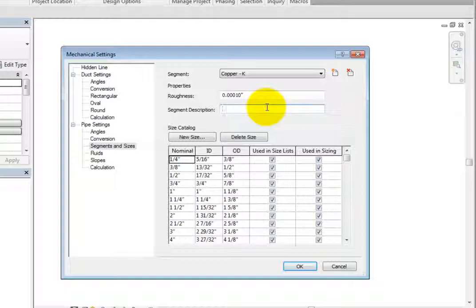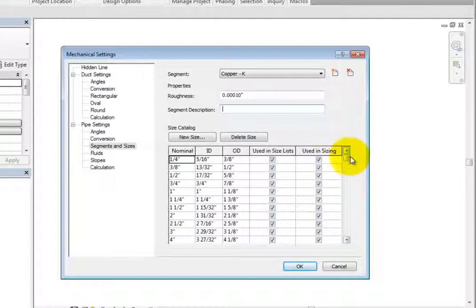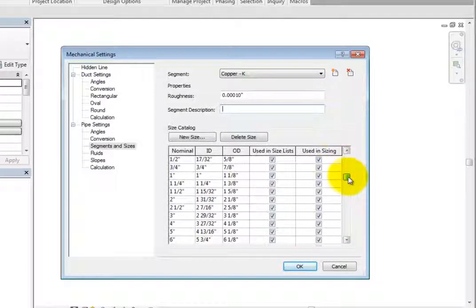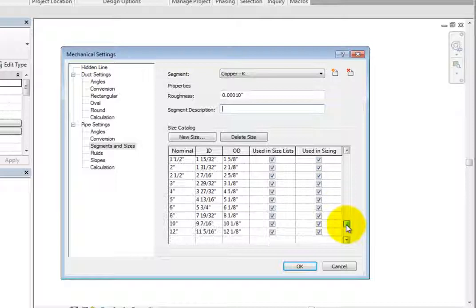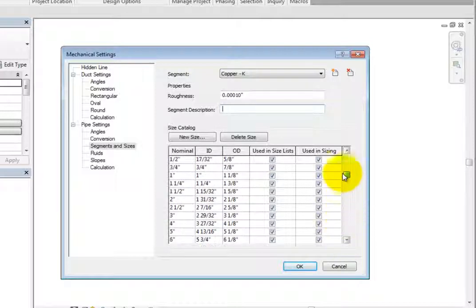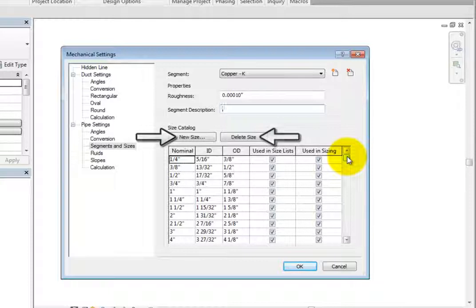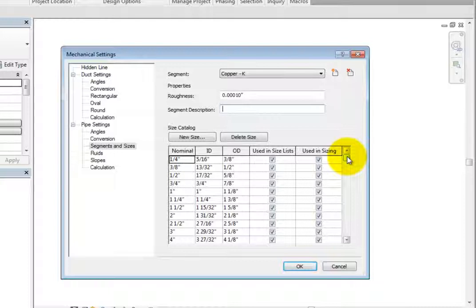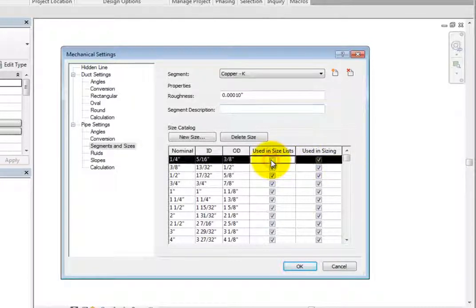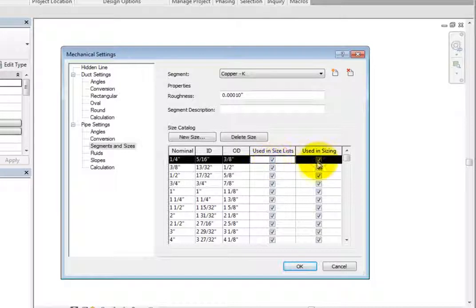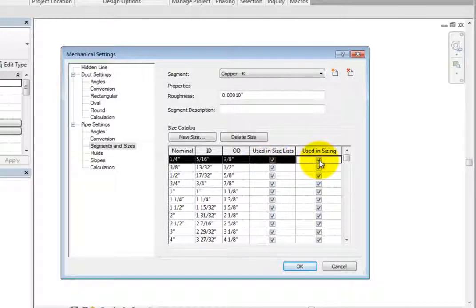Lastly, you can control the sizing for the segment. In the Size Catalog area, the nominal size is shown along with the ID, or Inside Diameter, and the OD, or Outside Diameter. These values cannot be changed. However, you can add a new size or delete a size. You can also control the pipe sizes that can be specified from the Options bar when creating piping, and also if a certain size will be used if Revit automatically sizes the piping.